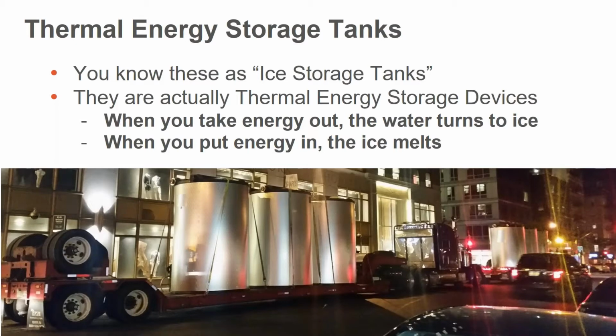Now, most of the people in the audience probably know these tanks. They are normally referred to as ice storage tanks. About 10 years ago, a purist wrote me a letter saying, your tanks don't store energy. And he's actually right. The ice tanks don't store energy. It's really the reverse. When you take the energy out, the water turns to ice. When you put energy in, you're charging it with energy, and now the ice melts. So it's the complete opposite of what we've always been saying, charge the tanks, discharge the tanks, but we were charging them with ice. But now we're talking about energy. So we're looking at these as thermal storage devices, and we're going to be storing either heat or cooling, depending on which way the energy is flowing and what you really need.